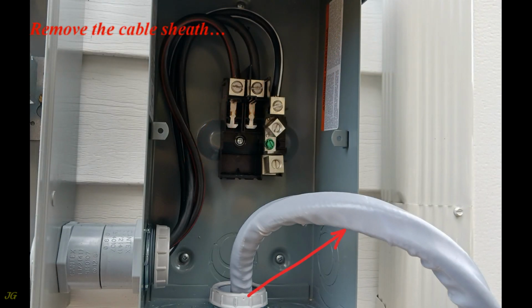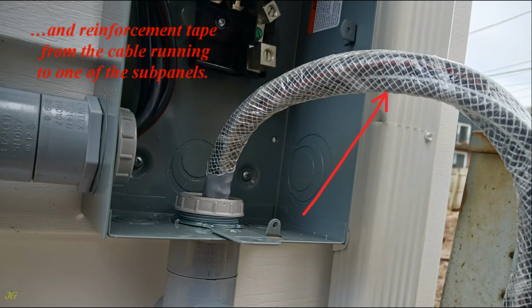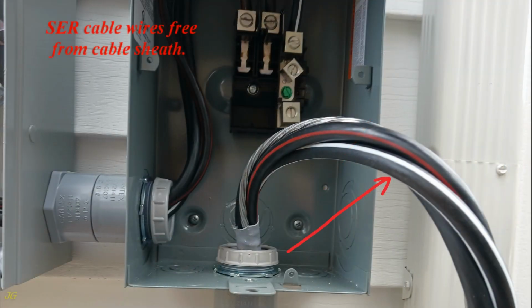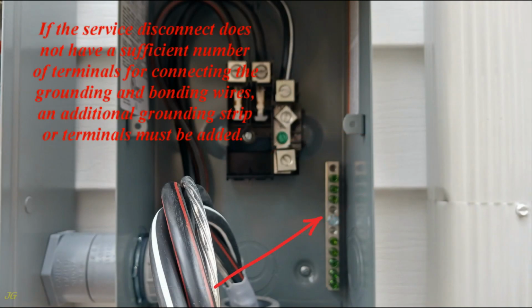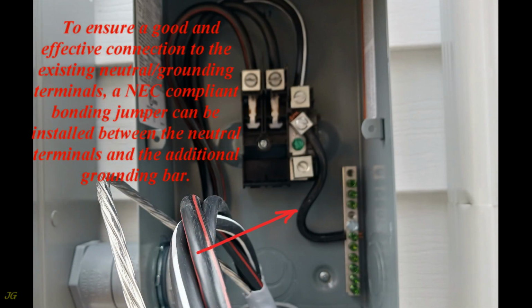Remove the cable sheath and reinforcement tape from the cable running to one of the subpanels. SER cable wires free from cable sheath. If the service disconnect does not have a sufficient number of terminals for connecting the grounding and bonding wires, an additional grounding strip or terminals must be added. To ensure a good and effective connection to the existing neutral, grounding terminals, a NEC-compliant bonding jumper can be installed between the neutral terminals and the additional grounding bar.